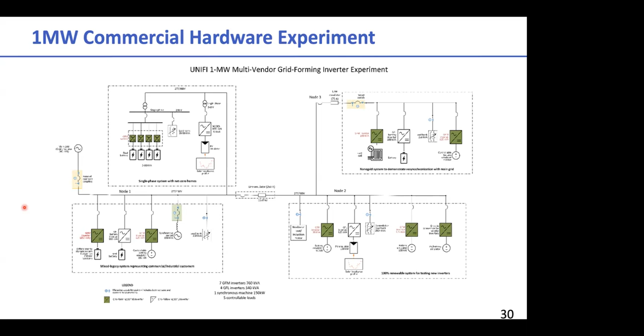In addition, we're looking at large-scale demonstrations of grid forming technologies. If you're not familiar with this example, this is Kauai Island, one of the Hawaiian Islands, the furthest to the west of the chain. The grid on this island is operated by the Kauai Island Utility Cooperative, or KIUC. It's really one of the only places in the world where large-scale grid forming technologies are actually deployed and being evaluated.